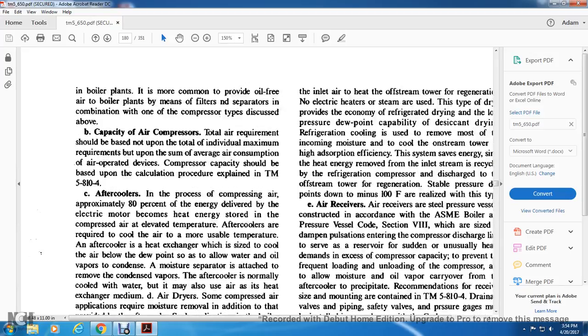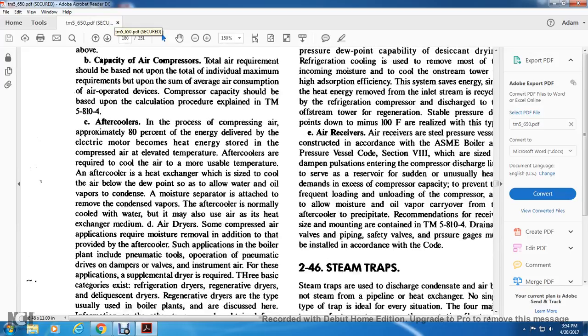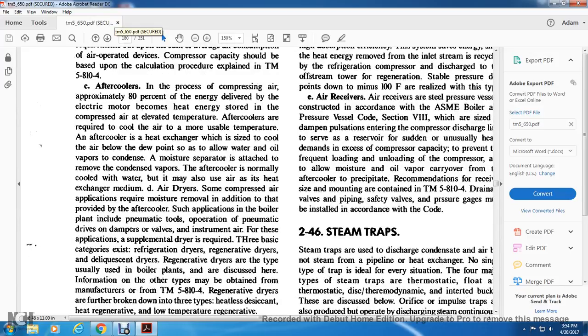After compressing the air, approximately 80% of the energy delivered to the electrical motor becomes heat energy stored in the compressed air, with the air at an elevated temperature. Aftercoolers are required to cool the air to a more usual temperature. Aftercoolers use heat exchange to cool the air below the dew point so as to allow the oil vapor to condense. A moisture separator is attached to remove the condensed vapor.